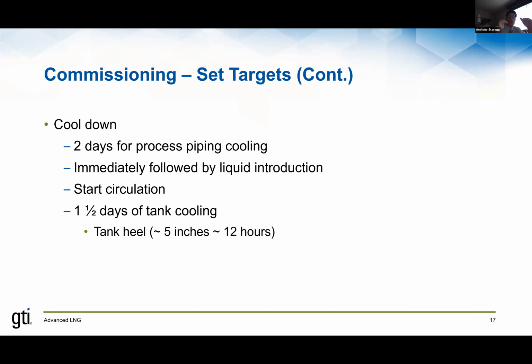What that means is you're introducing liquid into the tank very, very slowly. That liquid is cold. It's being introduced into a warm tank, and initially that LNG just vaporizes, right? And as the LNG vaporizes, it cools off the tank. As it cools off the tank, you'll get to a point where you'll start actually having LNG remain as a liquid. Once that happens, the liquid level will build up slowly as the tank continues to cool down. So the target here is about 5 inches of liquid in a tank after 12 hours of cool down.